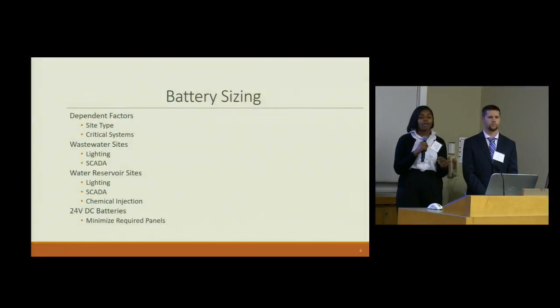For battery sizing, the dependent factors were site types and critical systems. The critical systems vary based on the type of site. Wastewater sites have both lighting and SCADA, whereas water reservoir sites have lighting, SCADA, and chemical injection.